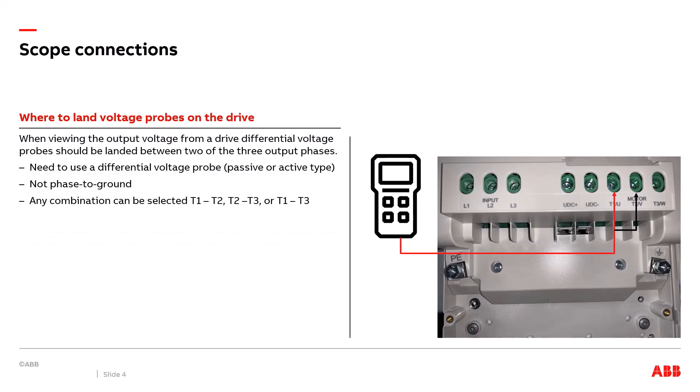We're first going to discuss what the output voltage waveform looks like on an oscilloscope. We need to hook up voltage probes to the output terminals T1, T2, and T3. It's important to use a differential voltage probe — active or passive. We hook up the probe between any two terminals: T1 to T2, T2 to T3, or T1 to T3. We do not hook up between T1, T2, or T3 and ground. We're referencing phase to phase, not voltage to ground.